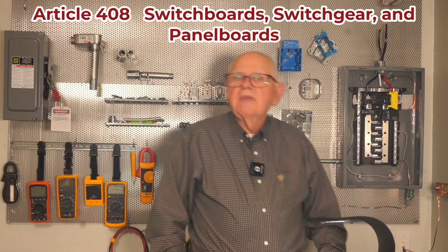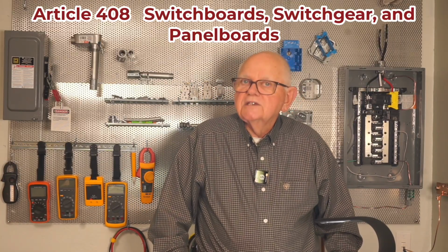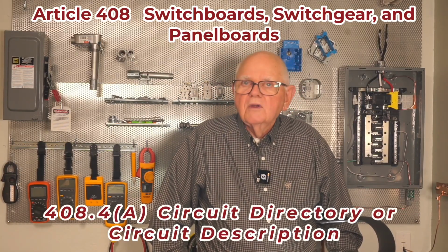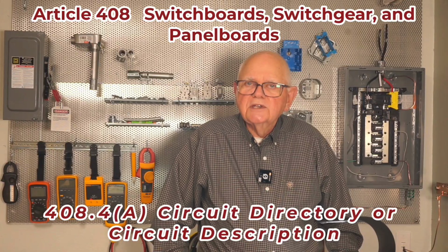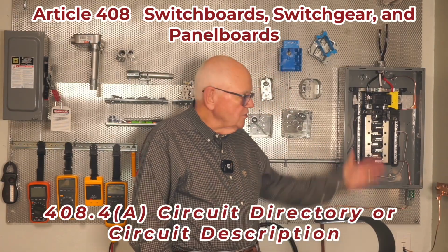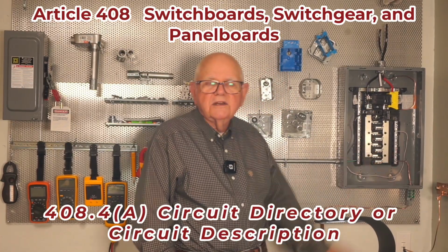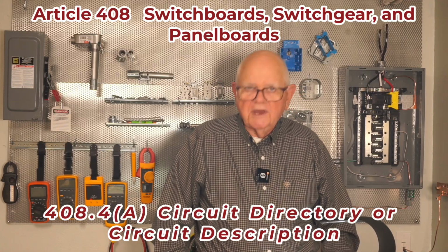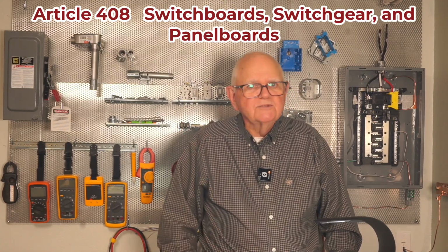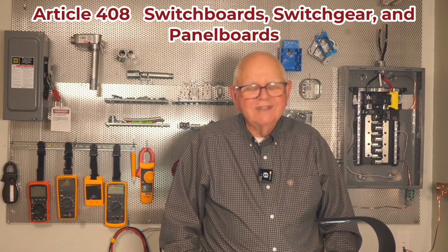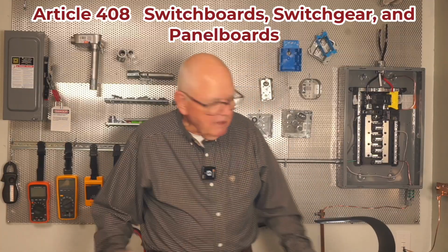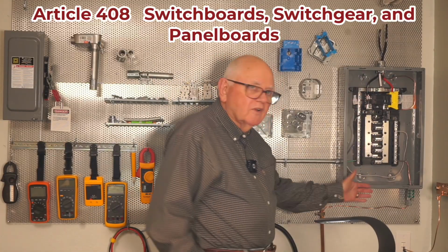Also in your panel board, you must identify any spare breakers. So if I have any spare breakers in there without loads connected to them and they're just breakers mounted in there, I have to identify them as spares, right? All part of making sense when we read that circuit directory, doesn't it? Right? Orientation, my panel boards must be mounted vertically.